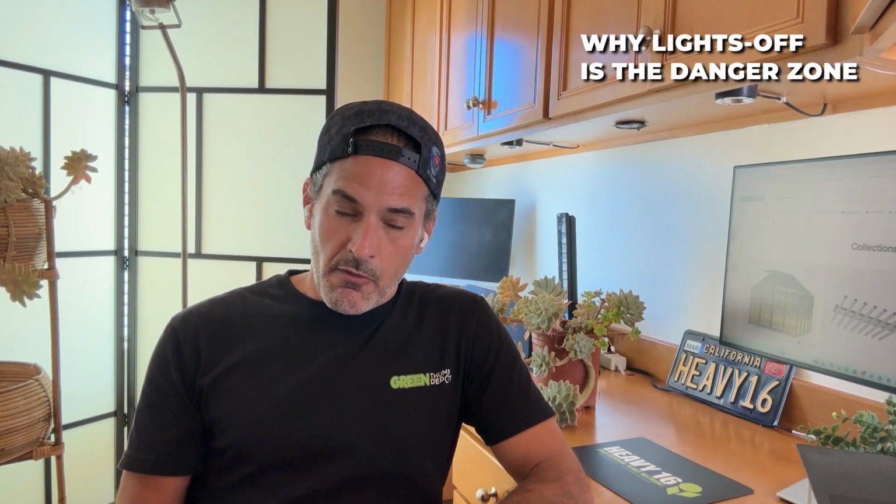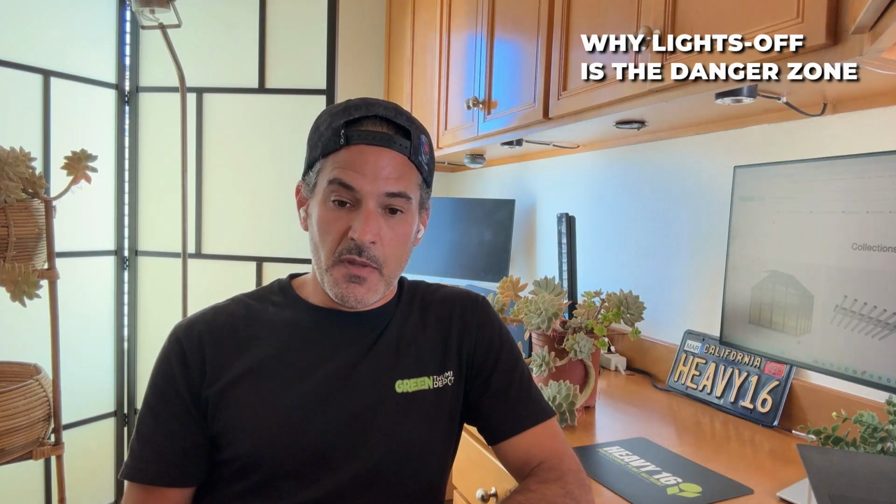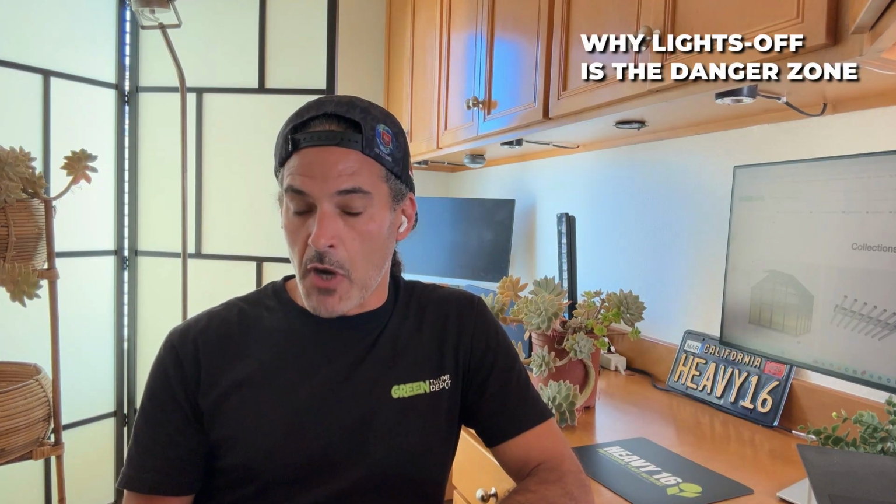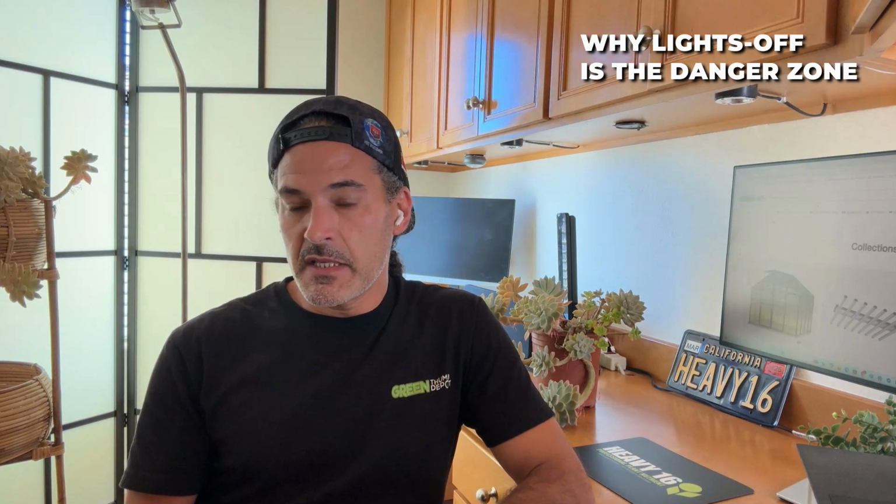Okay, so Elliot, why is there such a demand for increased dehumidification when the lights are turned off? Yeah, there's a few reasons actually. First of all, when the lights turn off, the temperature of the room drops dramatically. So the air conditioning units will turn off at some point. The air conditioning units are providing some dehumidification, so you're losing that dehumidification.